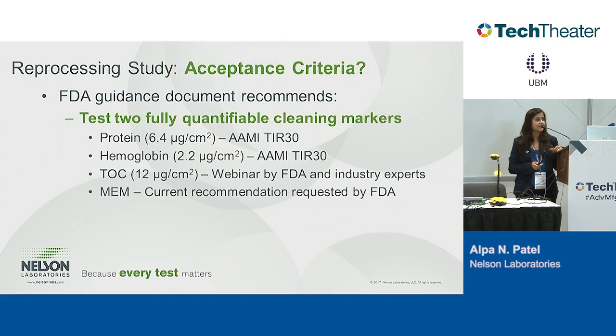Some of the acceptance criteria for these validations: the FDA likes to see at least 2 fully quantifiable assays, which the guidance document goes into in detail. Protein, hemoglobin, and TOC are the top 3 that are recommended. Now, TIR30 has all these markers established. These were developed through a study that was performed on endoscopes, and since the endoscope is considered the worst case device in the industry for reprocessing, you can use that benchmark to leverage for other reusable medical devices.